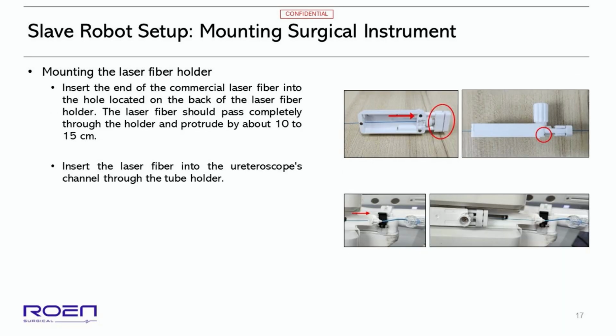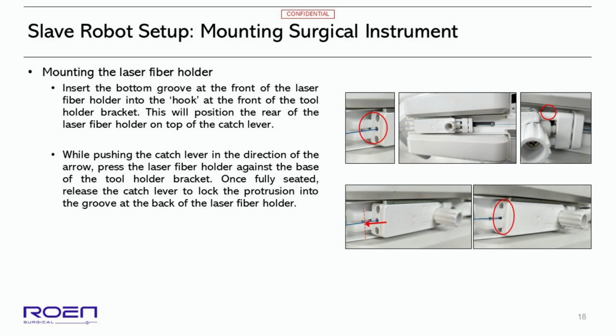Mounting process for the laser fiber holder. Insert the end of the commercial laser fiber into the hole located on the back of the laser fiber holder. The laser fiber should pass completely through the holder and protrude by about 10 to 15 cm. Insert the laser fiber into the ureteroscope's channel through the tube holder. Insert the bottom groove at the front of the laser fiber holder into the hook at the front of the tool holder bracket. This will position the rear of the laser fiber holder on top of the catch lever.